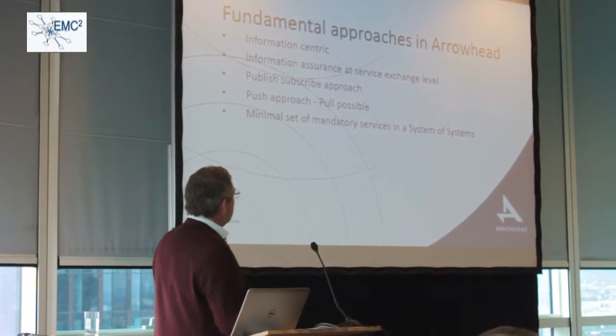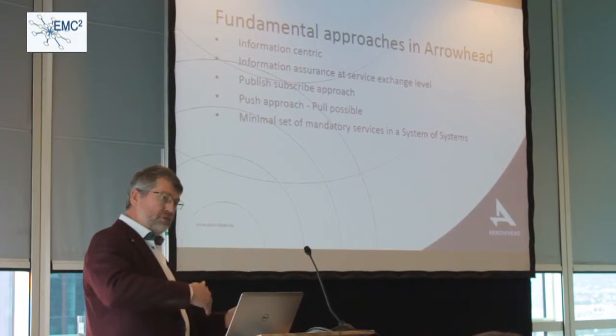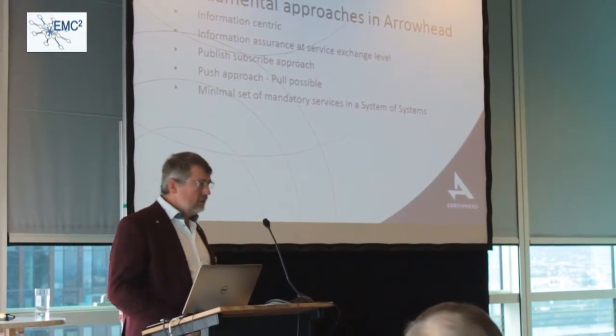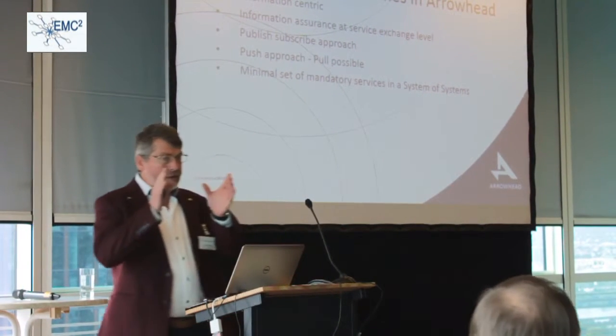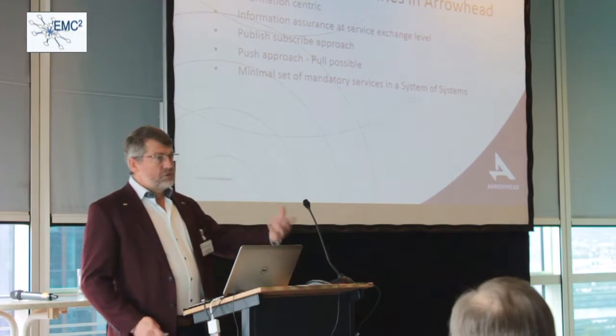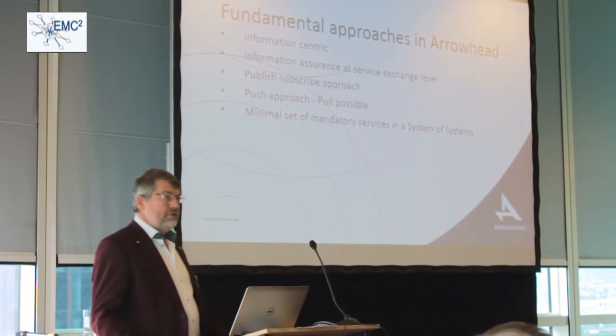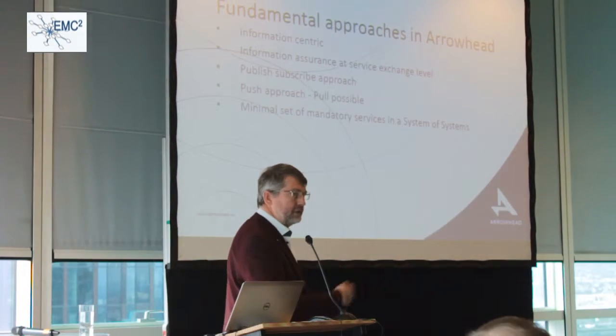Most of the situation is that it's publish and subscribe. So you say, okay, I'm here, someone can subscribe to your information. Either say I want it every 10 milliseconds, or I want it just when pressure is higher than something, or temperature is higher than something, or energy usage is higher than something, or in a window of certain interest, and so on. Which means that data most often is pushed to someone on a certain event. You can even design this system to do pull, which is the traditional way of doing so: I'm reading data every 20 milliseconds.